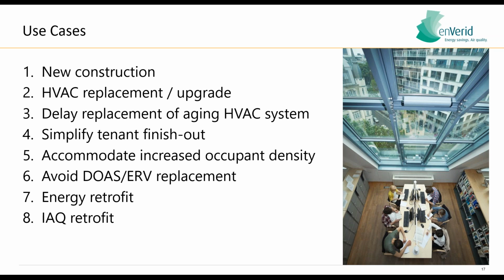One use case is where you have a change of purpose of the space. Let's say you had an office and you suddenly add occupants, maybe transforming the office into a WeWork type of space or a call center. In this case, you have two solutions. One is you retrofit your building and rip out your existing DOAS units or air handling units and add capacity. Or alternatively, you say, this is how much outside air I currently have, and I supplement the rest of the outside air needed with air cleaning. This is also similar if you have a project with a certain energy efficiency requirement, or it's a geothermal project where you cannot drill more wells, so you substitute the rest of the ventilation with air cleaning.